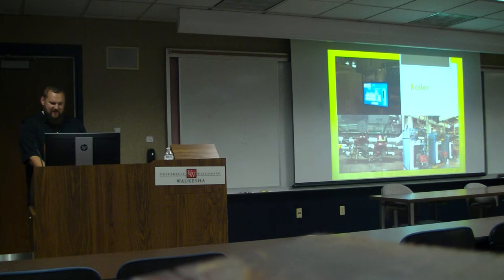You can see in the lower right-hand corner the new boilers. Most people think there would be a boiler per building, but these are all located in one building, the fuel house, and pumps send heat throughout all the other buildings. Computer programs and the variable speed drives monitor the flow, letting it run at a certain rate instead of full speed all the time.